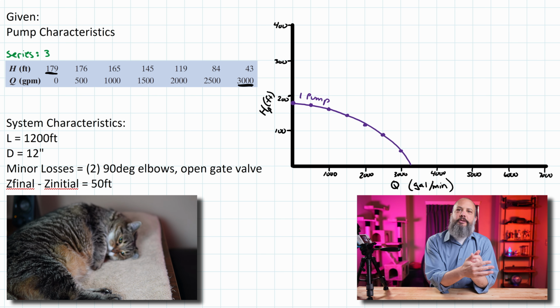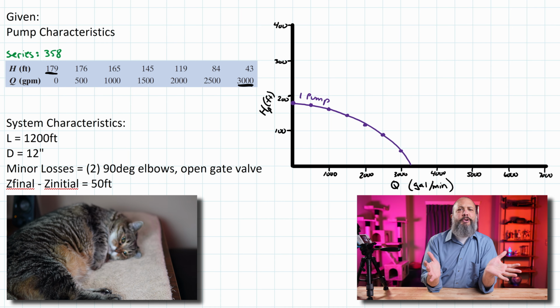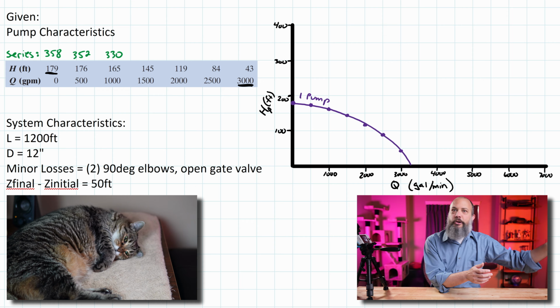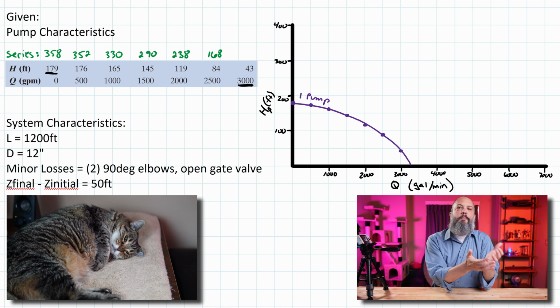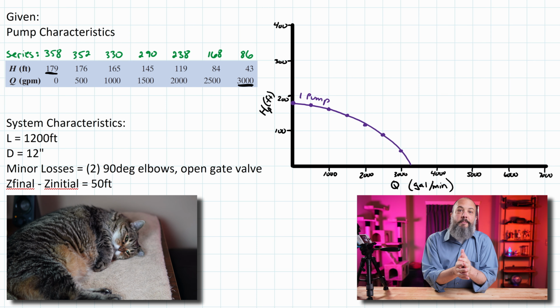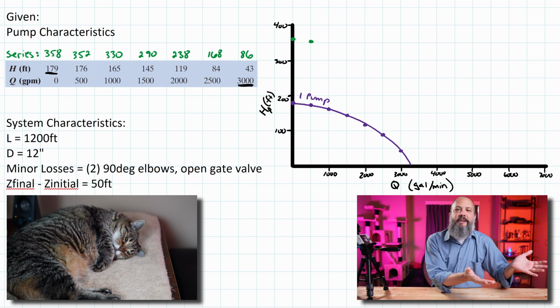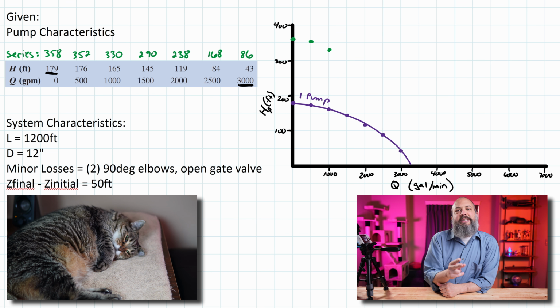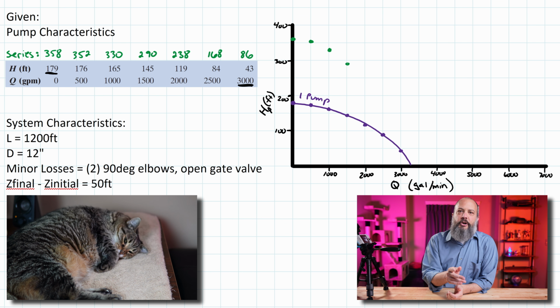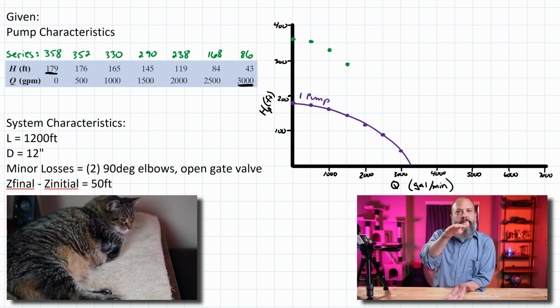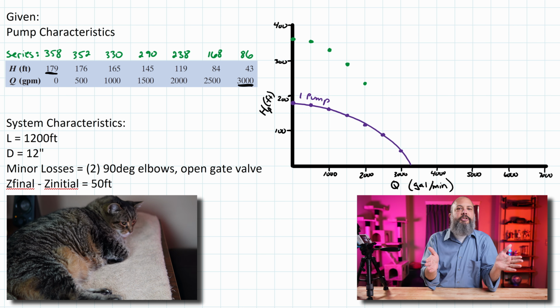When you place two pumps in series, one after the other, they're gonna have the exact same flow rate through them, right? That's the continuity principle, like conservation of mass. All of the water that goes through the first pump all goes through the second pump, right? The exact same amount of water, but the extra pump adds additional pump head. So if the first pump adds 179 feet of head, then the second pump also adds 179 feet of head. So when you place two pumps in series, your pump curve gets twice as tall, but its width doesn't change.